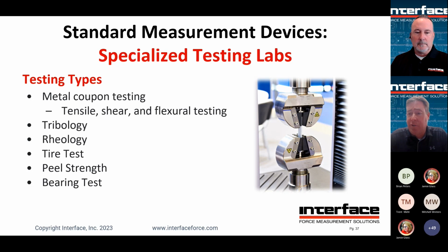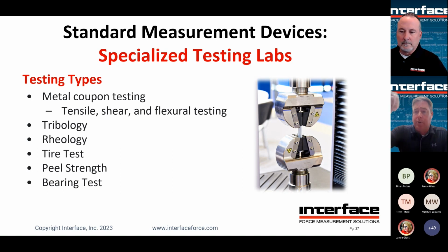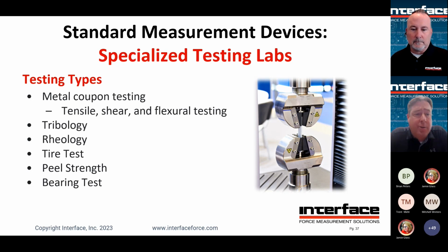Another subset here, tribology. It's friction. They're going to be applying a known load and then cycling a specific material against another material and analyzing those results. Load cells can be used there, are used there, I should say, to essentially apply that downwards force and measure the resultant force that's on the x-axis. Multi-axis load cells can be a good solution here because you get both the downwards force and the x force at the same time.